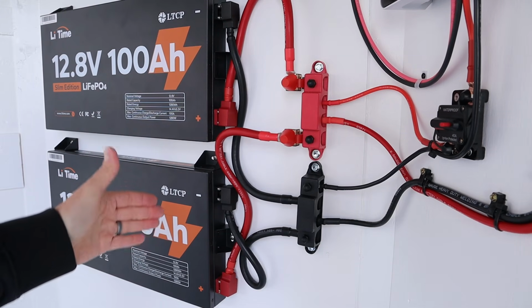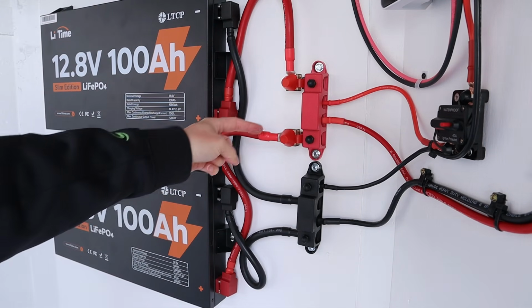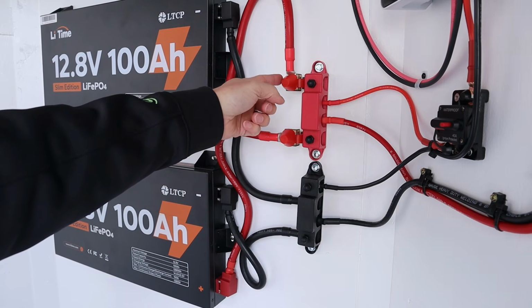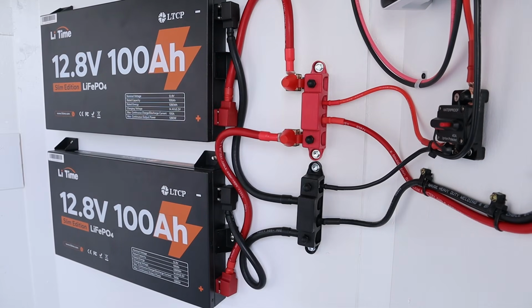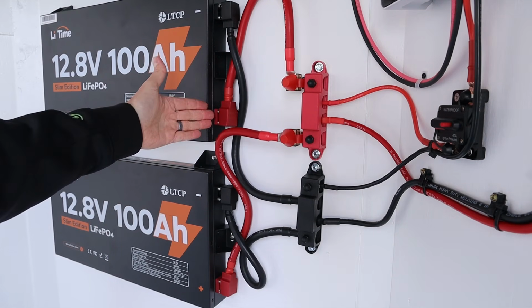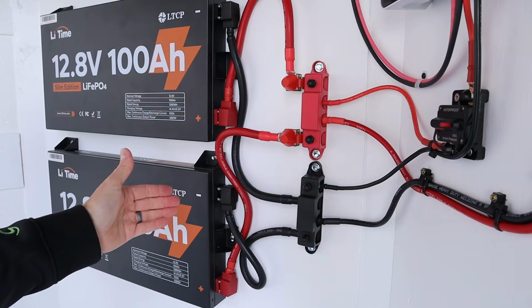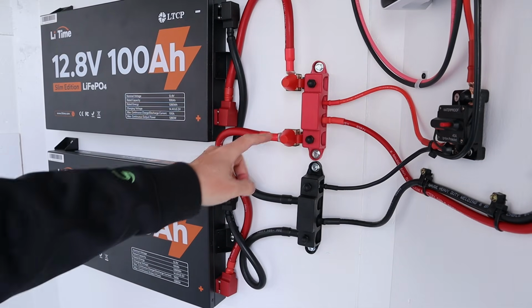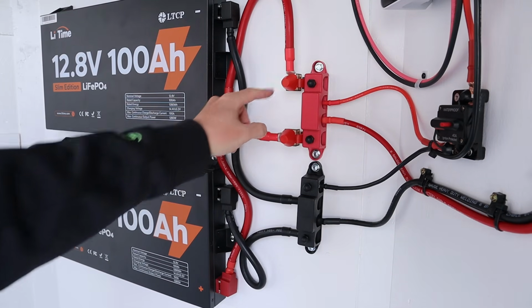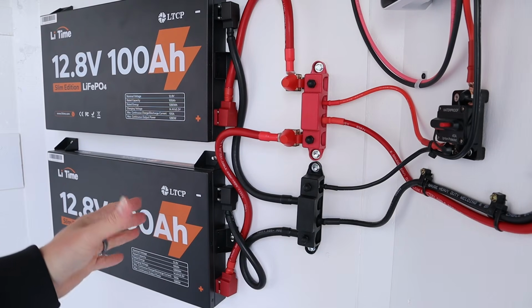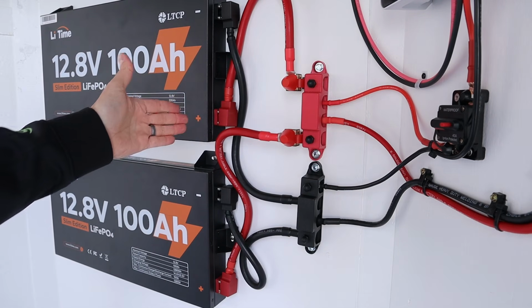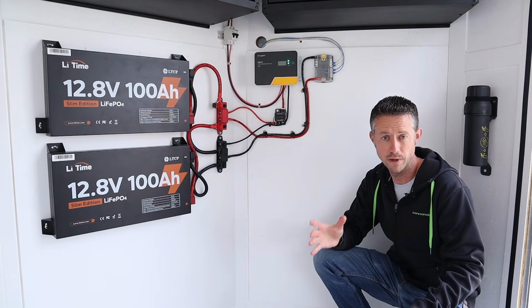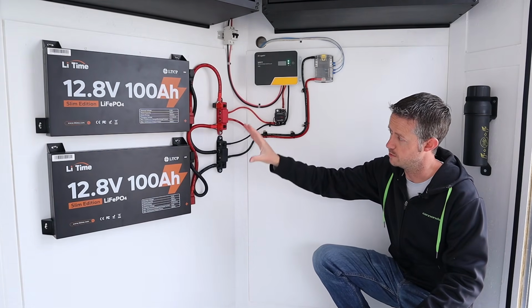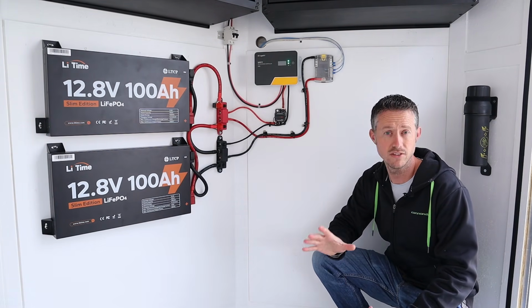The other downside with the 1/4 inch connections is that these 150 amp terminal fuses use 5/16. So I would have preferred to have them installed on the positive terminal directly, but because they're 1/4 inch, I had to install those here on the bus bar instead. It's not a deal breaker, but it's always best to have the fuse as close as you can to the battery itself. So that's basically the changes with my setup, at least the new changes with these batteries and the bus bars. Everything else is still the same.